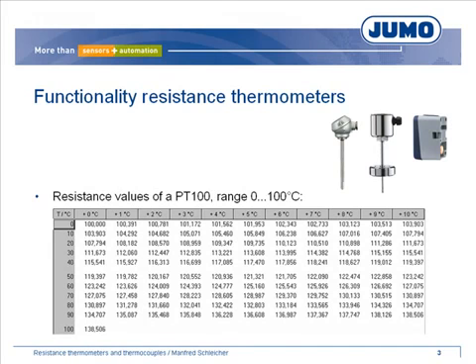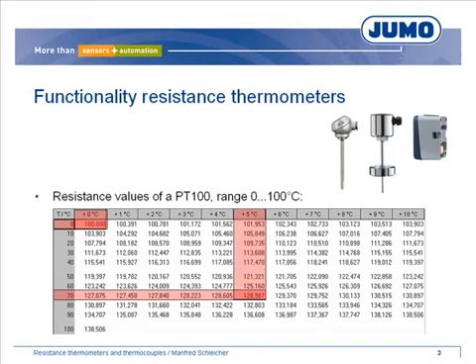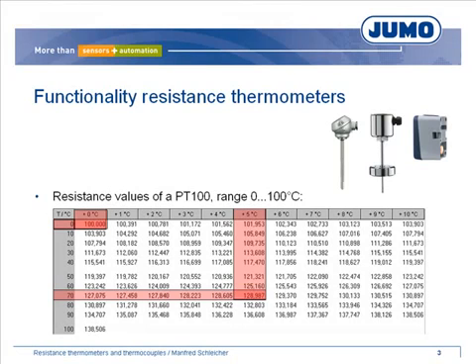The resistance value of a PT100 at 0°C is 100 Ohm. At 75°C, the resistance value is 128.987 Ohm. Furthermore, resistance thermometers like PT1000 with a basic resistance of 1000 Ohm, PT500 with 500 Ohm, and PT50 with 50 Ohm are used. Generally, all kinds of basic resistances are possible.